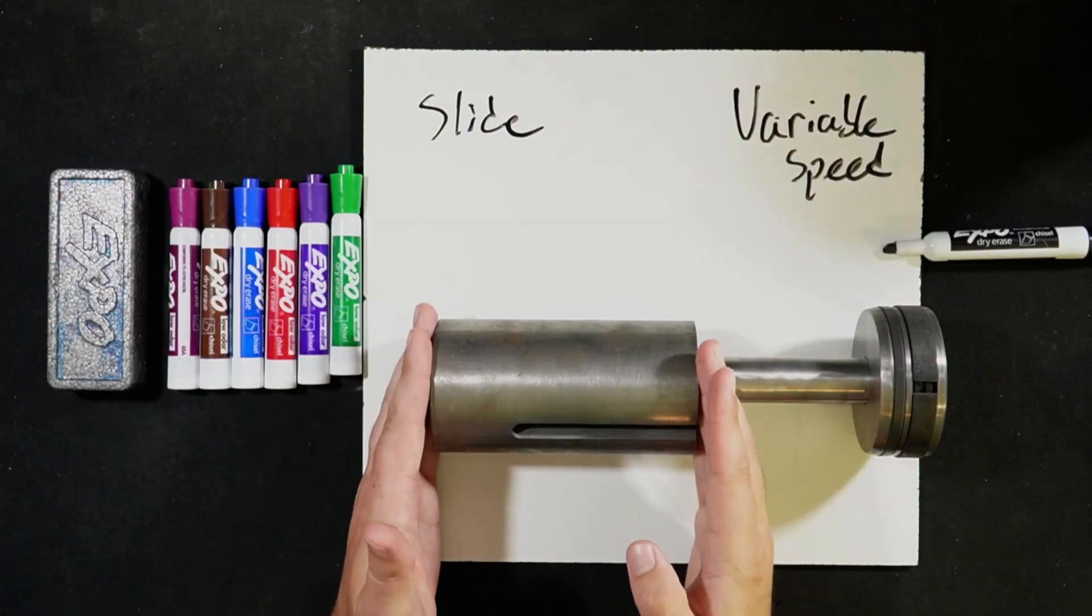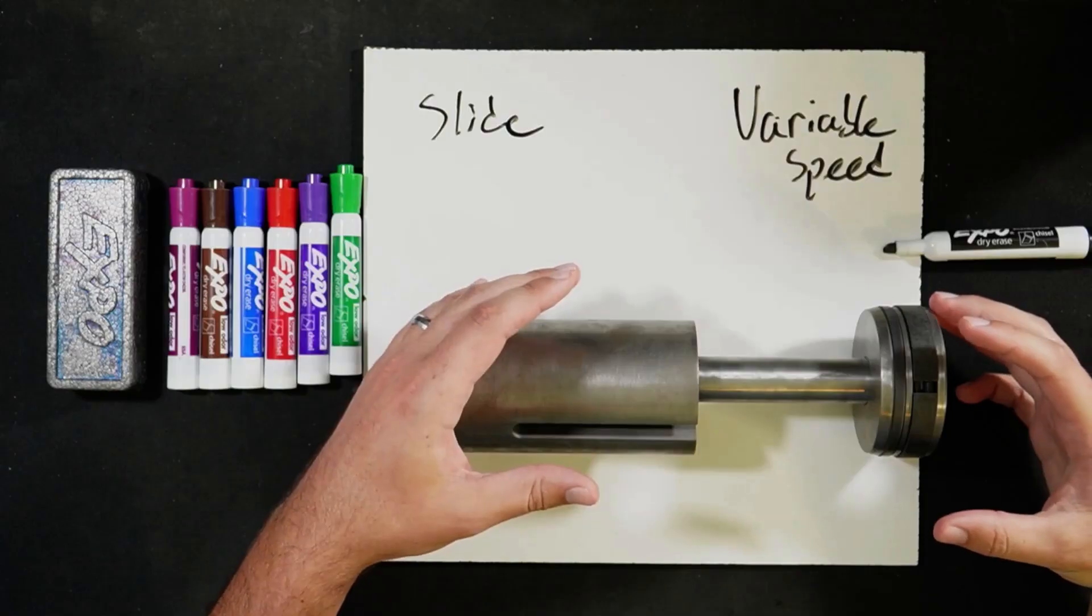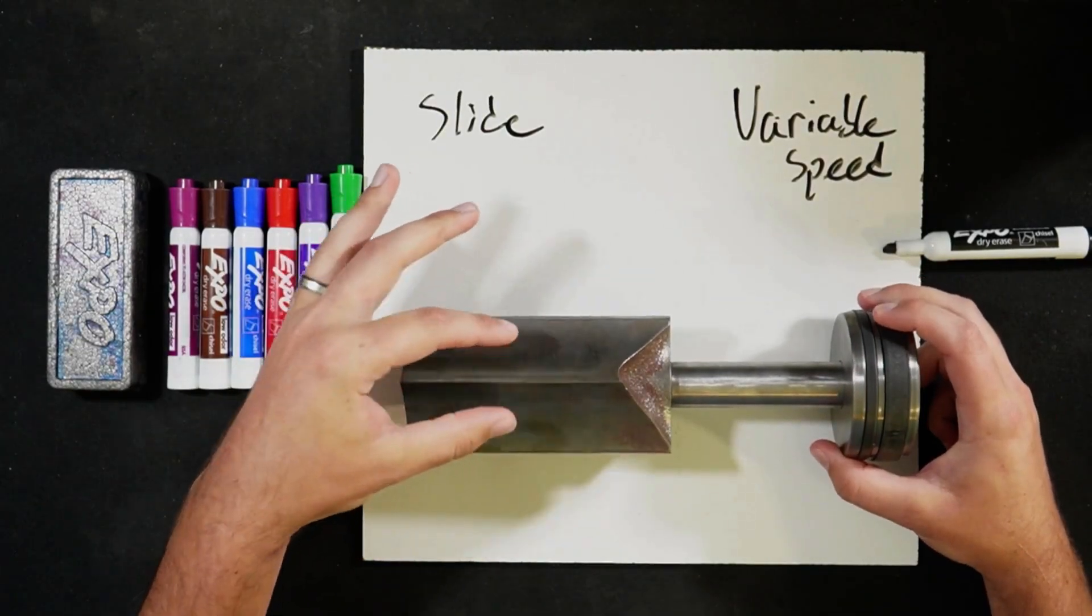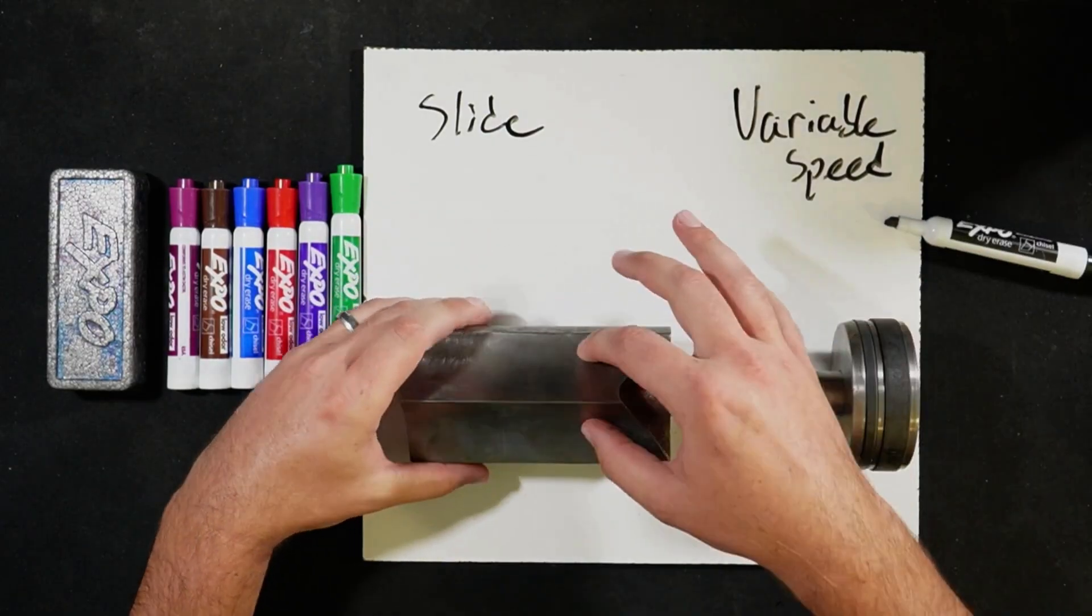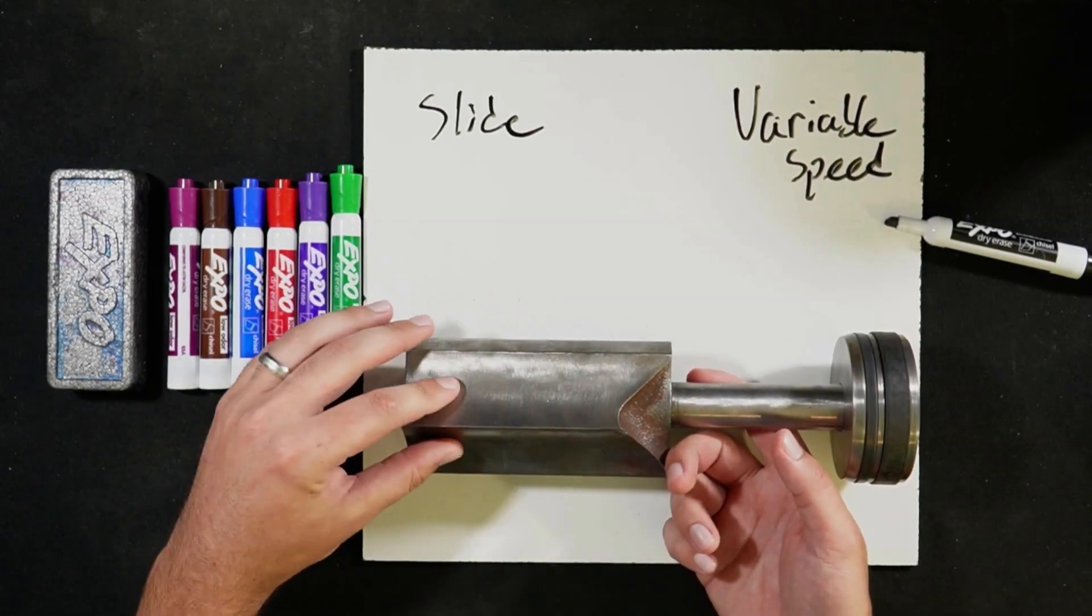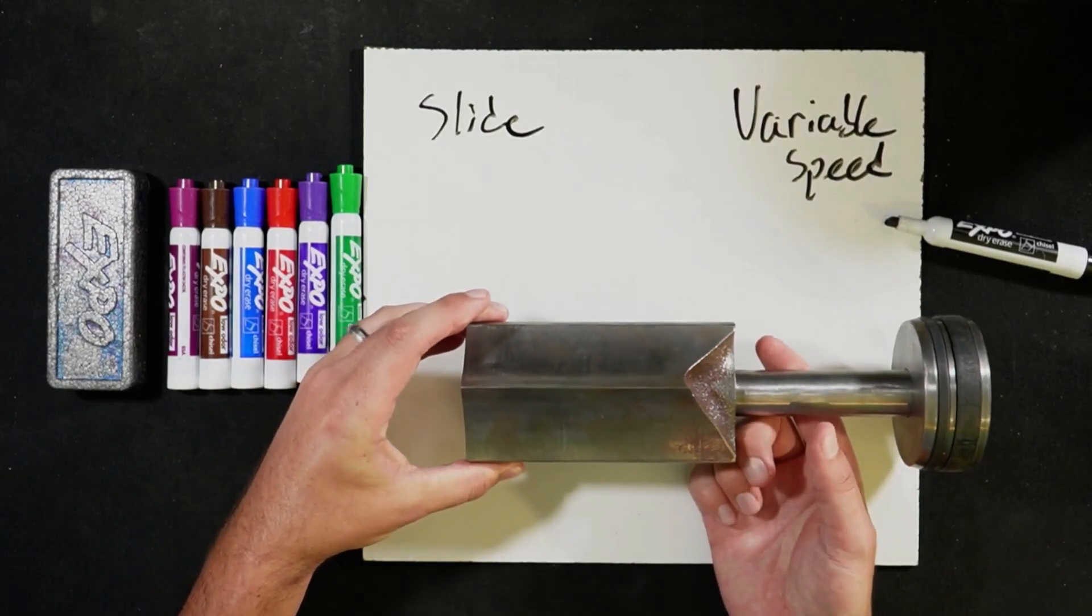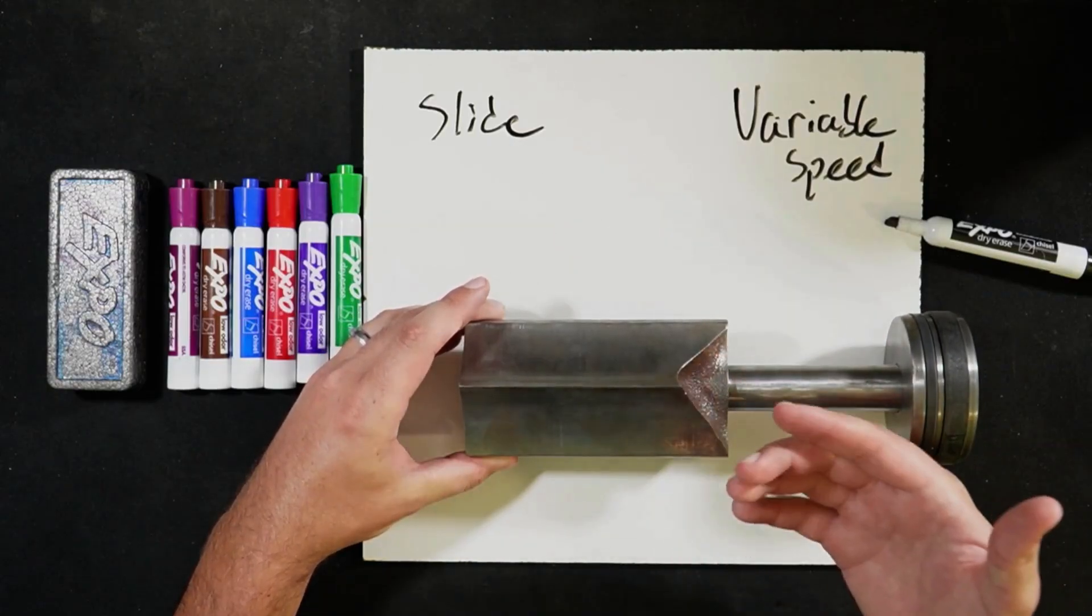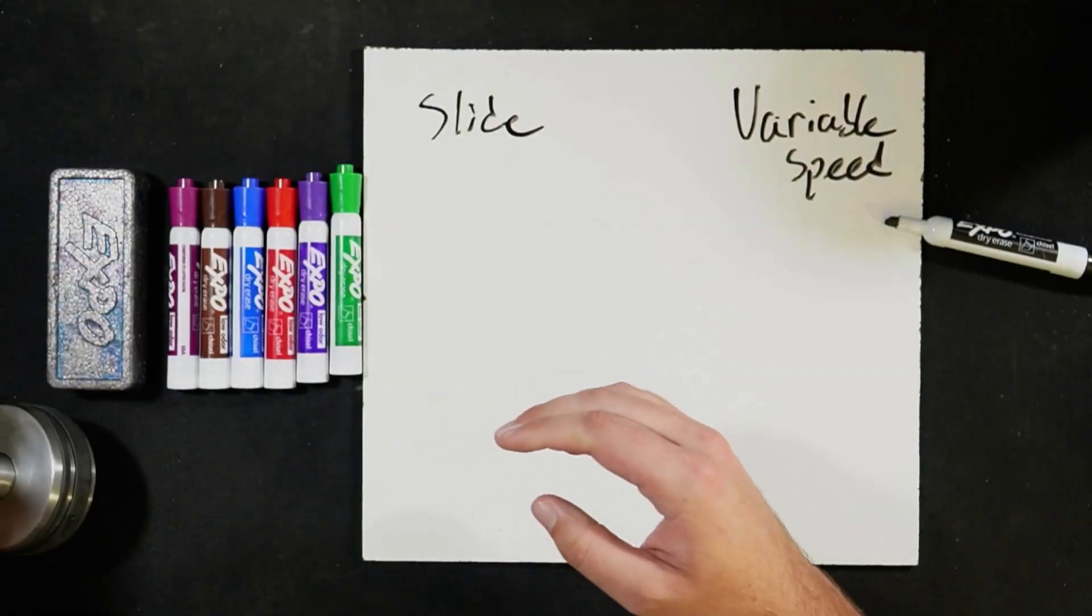This is what I'm talking about. Okay. So this is our actual slide. This is the shaft and this is our piston. This is our puck. This is our slide ring. There's various terms for it, but the way these work right here is where your male and female rotors would sit. So this part of it is actually creating a sealing surface for the screws to seal up against. And as this moves, not your screw bolts, but the actual slide here as this moves, we're adjusting the capacity by how much these screws are actually able to compress.